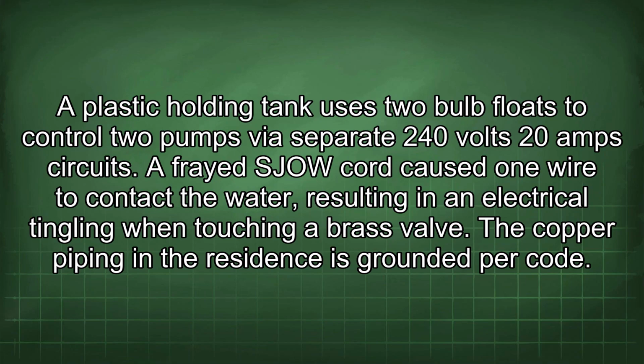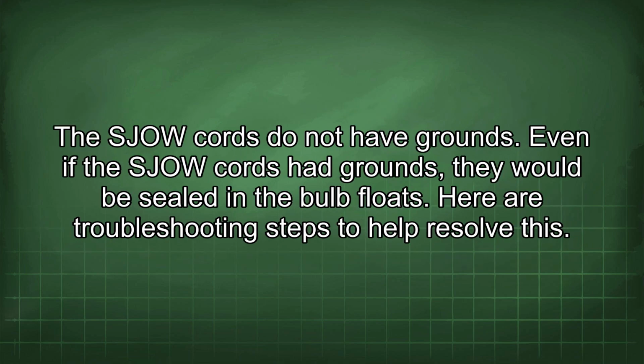A plastic holding tank uses two bulb floats to control two pumps via separate 240 volt, 20 amp circuits. A frayed SJOW cord caused one wire to contact the water, resulting in an electrical tingling when touching a brass valve. The copper piping in the residence is grounded per code. The SJOW cords do not have grounds. Even if the SJOW cords had grounds, they would be sealed in the bulb floats.